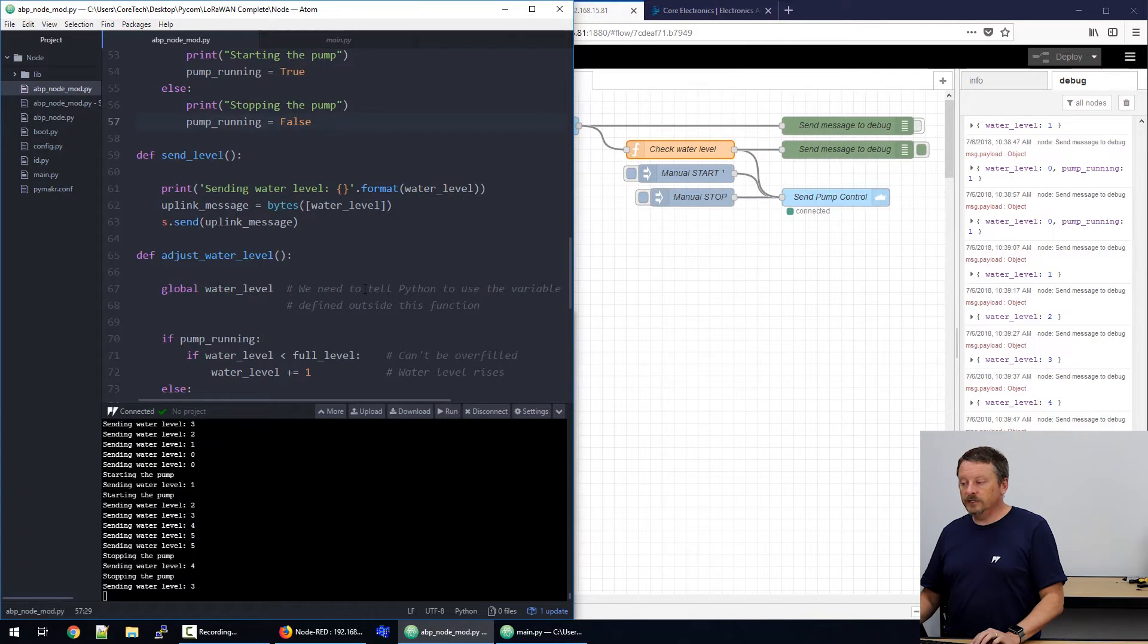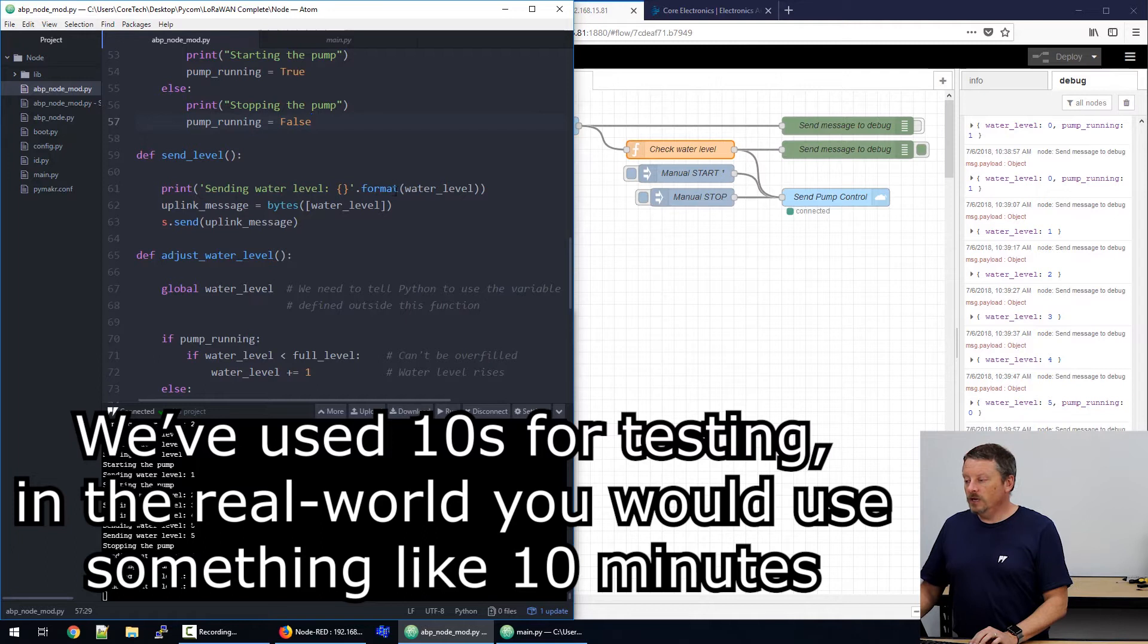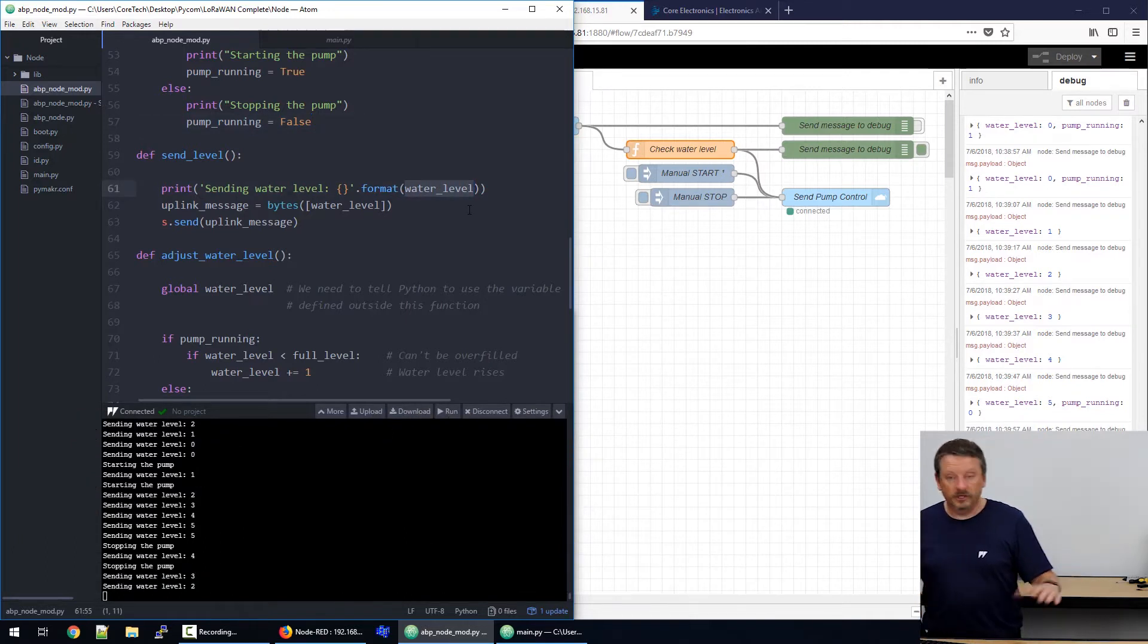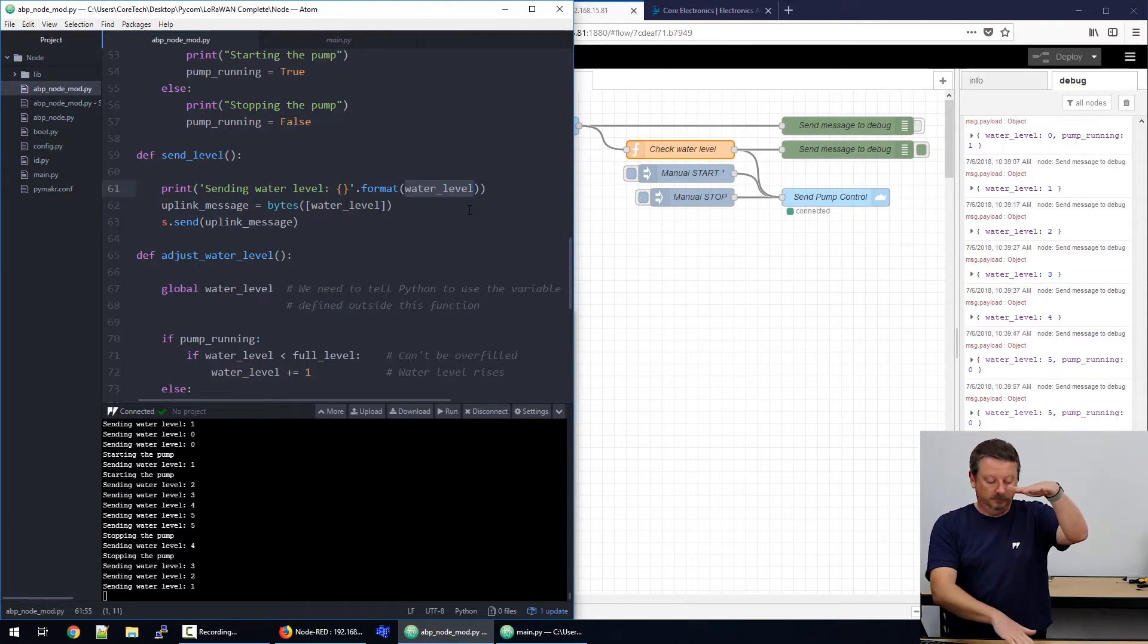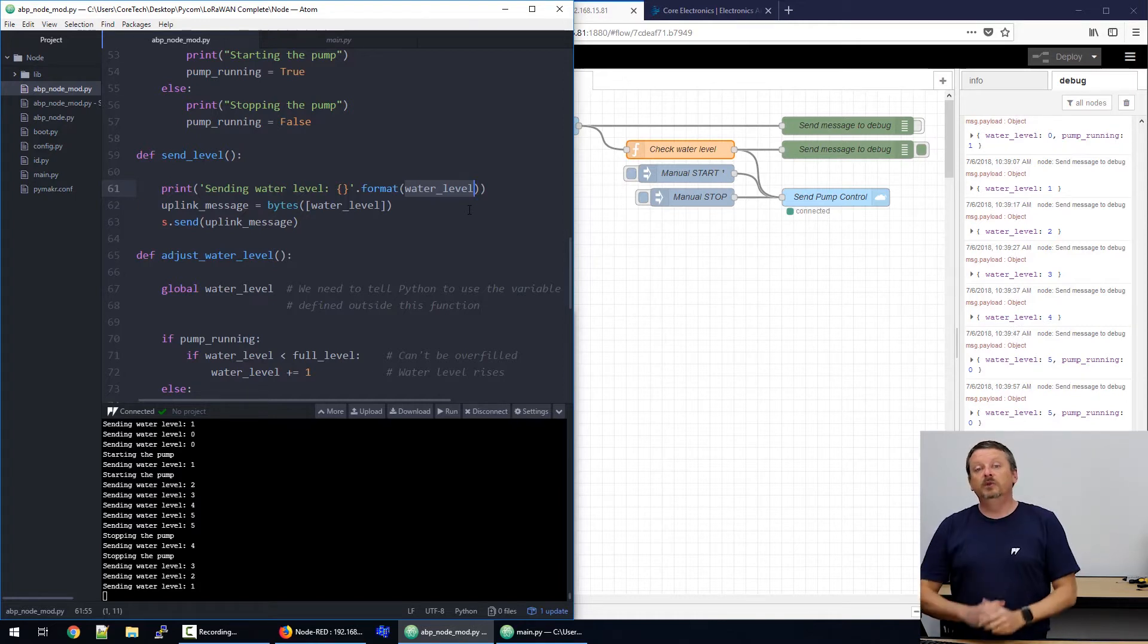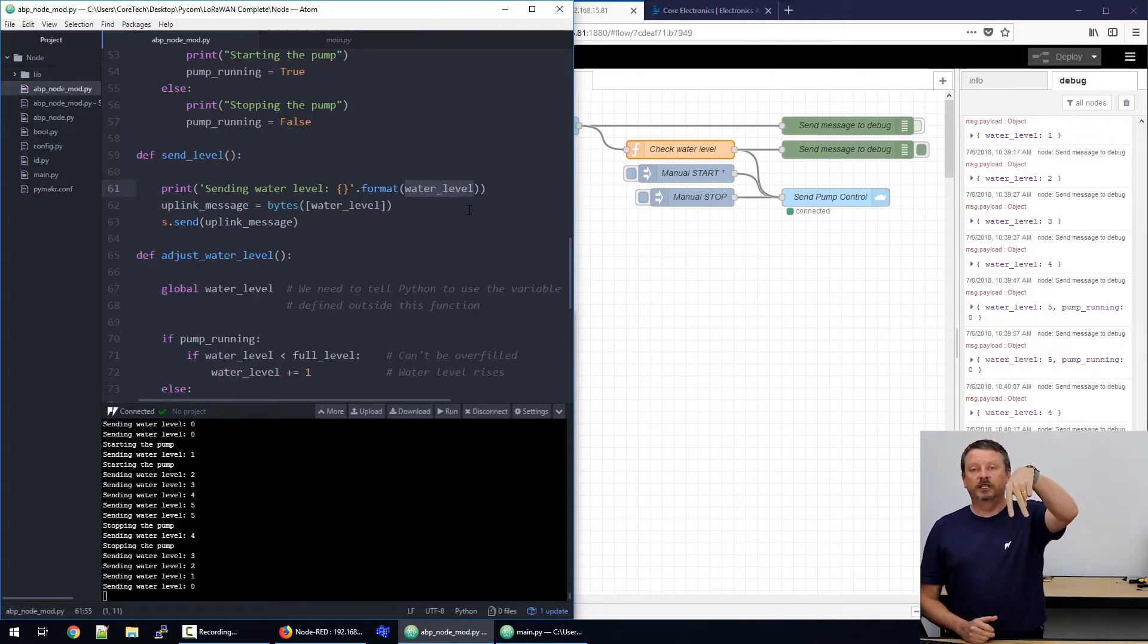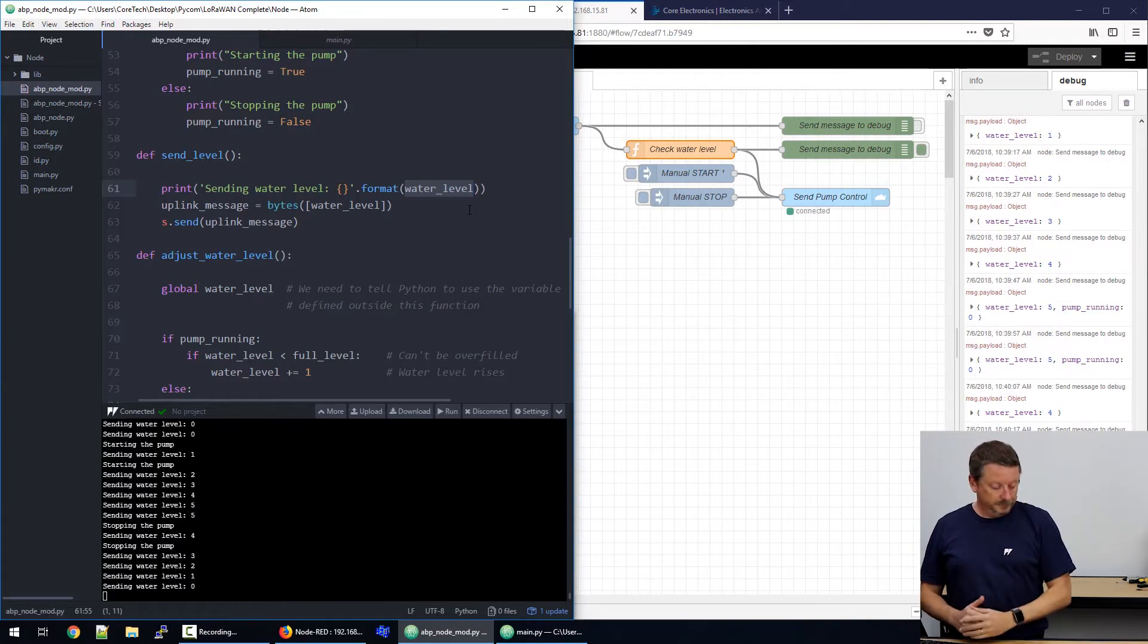We have a send level function here. And this is run every 10 seconds in the program. It would normally measure the actual water level. So, you could use an ultrasonic sensor, which you would position above the water. You bounce the ultrasonic wave off the water and it measures the height of the water. So, you get a continuous measurement from empty to full. Or you could use something like a conductance probe, which would sit at the top. And as the water level comes up and touches the probe, you know to stop the pump there because that's the top.